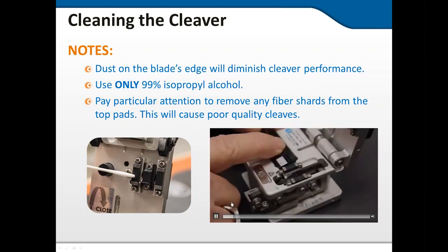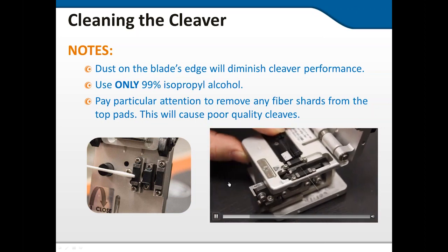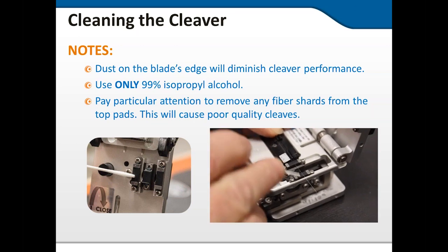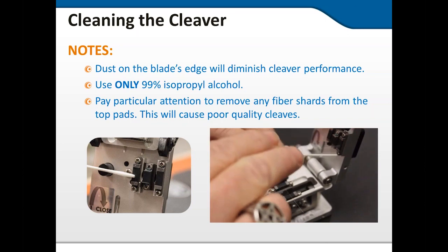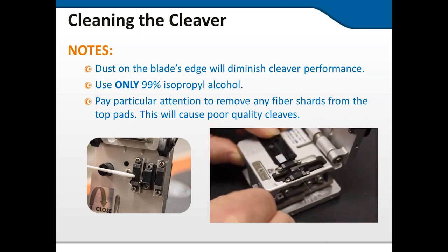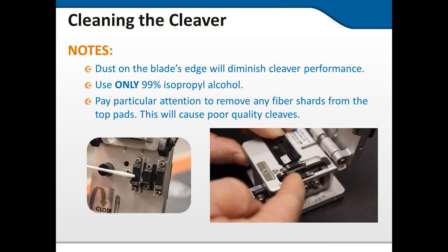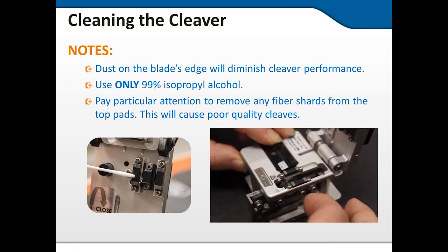Dust on the blade's edge will diminish cleaver performance. So very important, you just take the time, take a nice cotton swab and clean the top of the blade using 99% isopropyl alcohol. Pay attention to remove any fiber shards from the top pads. This will cause poor quality cleaves. So when I'm cleaving, I want to make especially sure that this pad and this pad are clean, because as the cleaver blade moves under, if these pads are not clean, the fiber itself can move, and I'll get an angled cleave rather than a straight cleave.